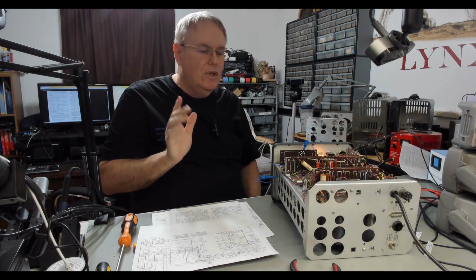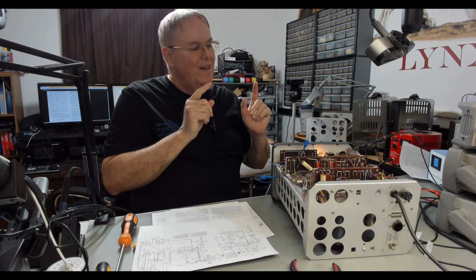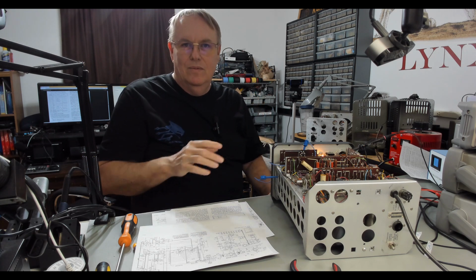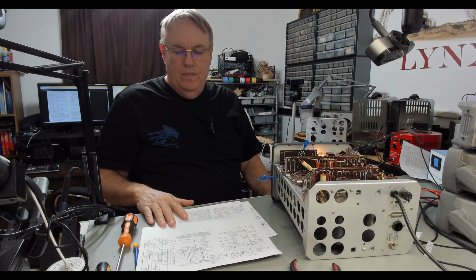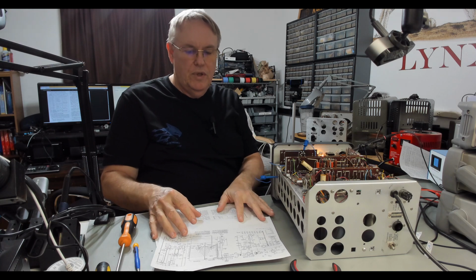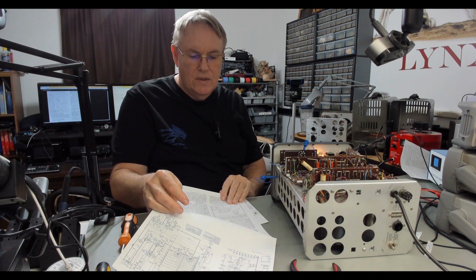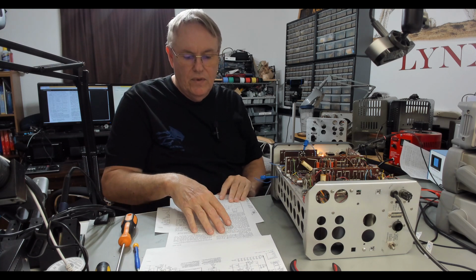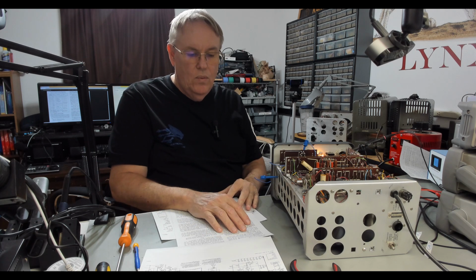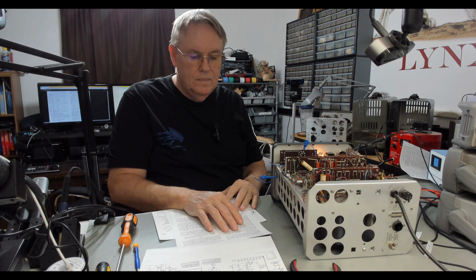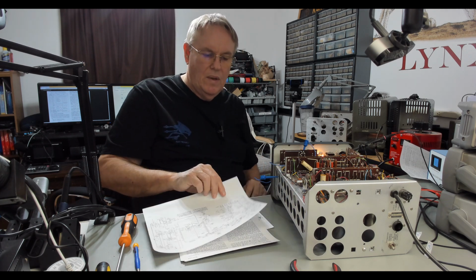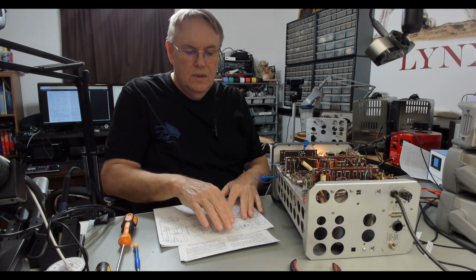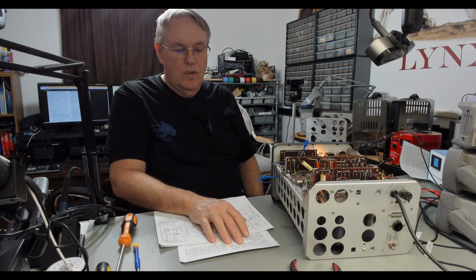So that's kind of good because I can't get another probe, but I can work on this device. So I'm going to do a little research. Let's see what it says. It says, if the signal is correct, check V8. If V8 is replaced, perform steps 16 through 19 of the adjustment. Waveform should be similar, except 180 out. Doesn't tell me why. Doesn't tell me what to do other than that, it thinks something's wrong with V8.